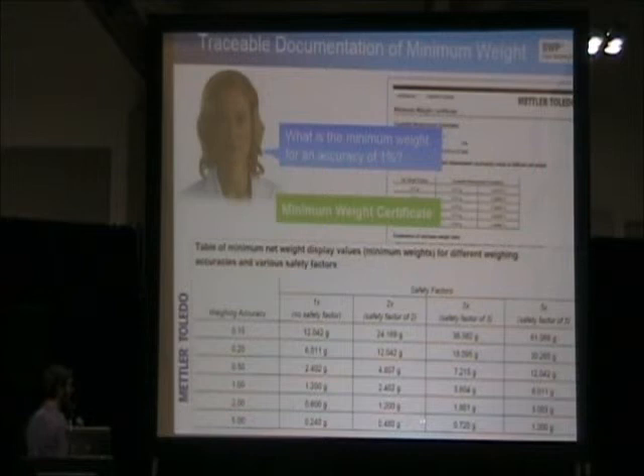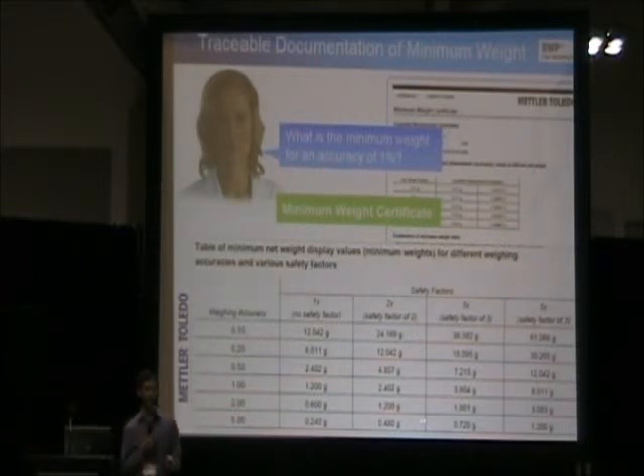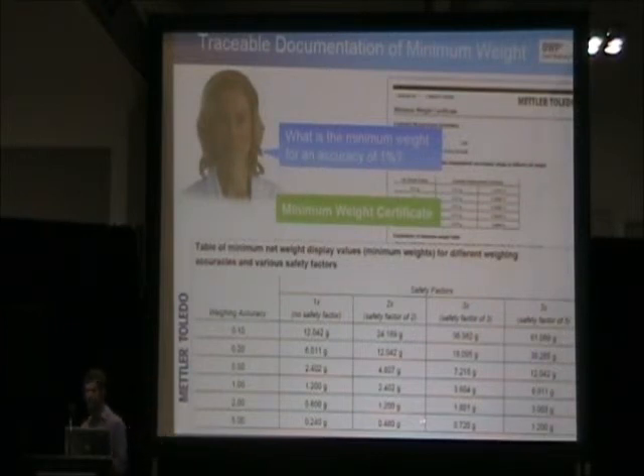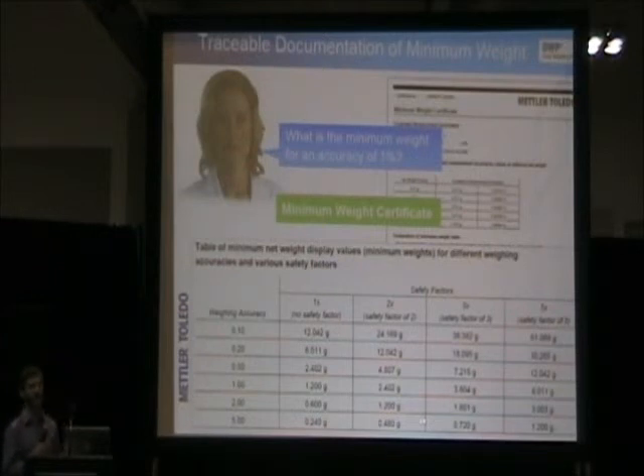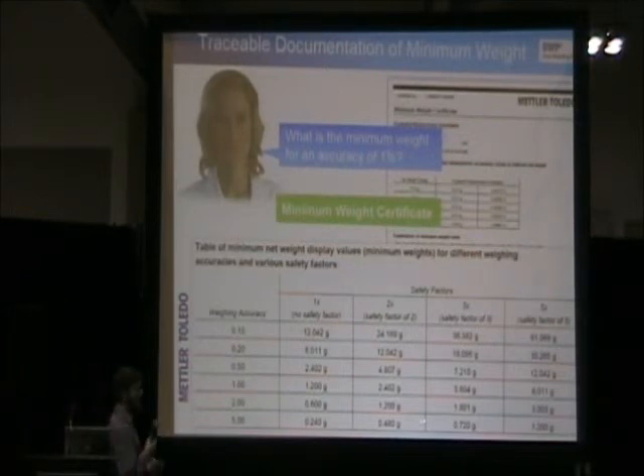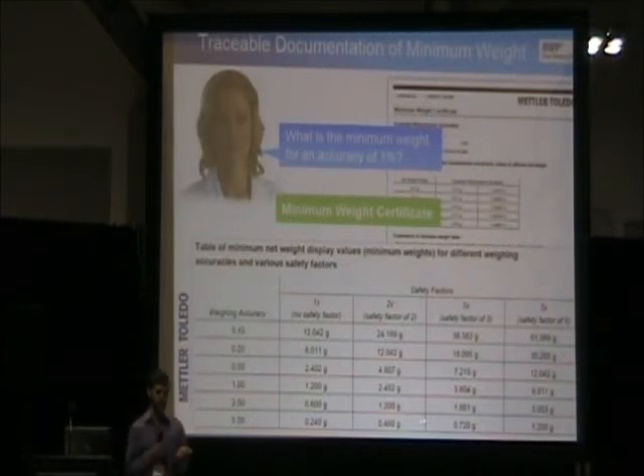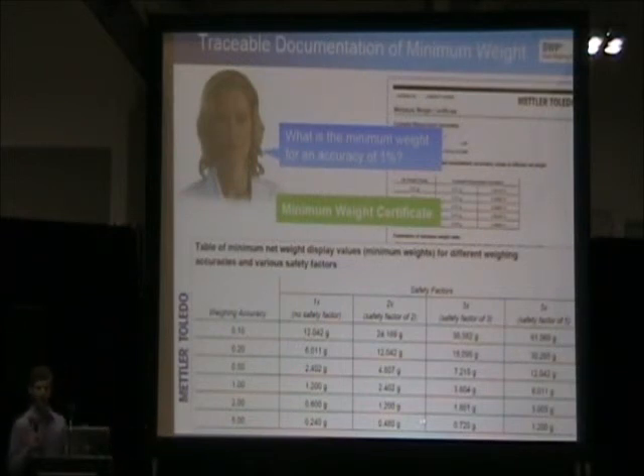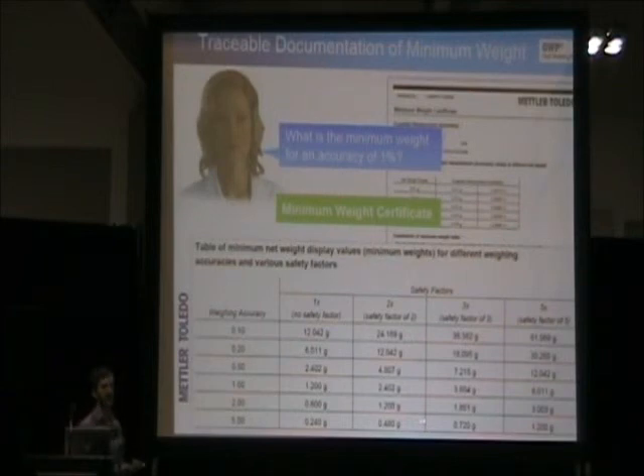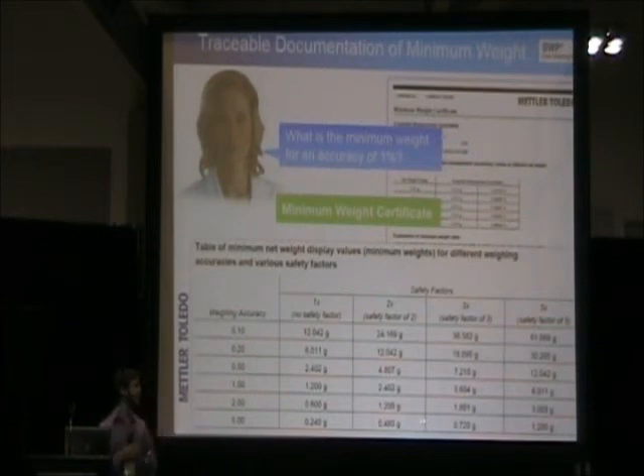And because of that reason, again, it's important that when you establish your minimum weight, you give yourself a relative level of safety. So as my prior example of 30 milligrams, if you were to take 30 milligrams and give yourself a safety factor of 1.5, you're looking at 45 milligrams. What that means is that if you have 45 milligrams in that particular instrument that tested to be able to perform at 30 milligrams when you performed your repeatability test, you're giving yourself 15 milligrams of room so that in case on, let's say, a Tuesday, it's very dry outside and the static potential is very high in your lab, you're ensuring yourself that you're not going to get below that 30 milligrams.